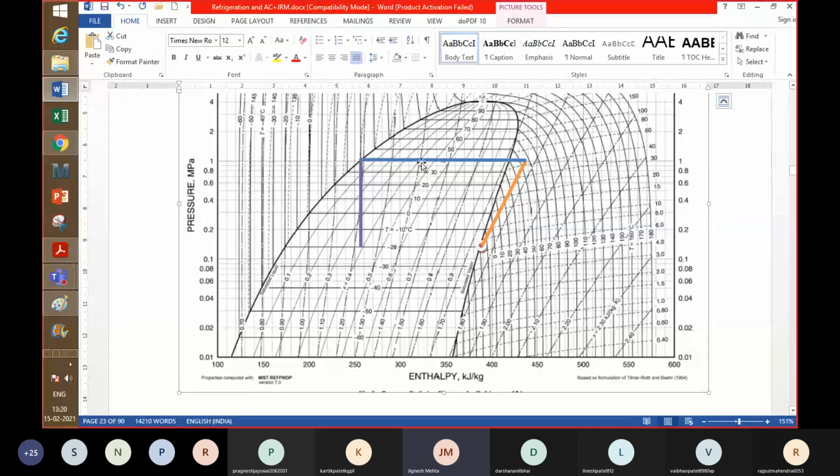Okay, and there could be other means also, but in a system where the pressure differential is not very high, you don't go for other means. Multi-stage compression could be possible, and at the end of the first expansion stage you take out the vapor, or such things are possible in an advanced VCR cycle. But if it is a small system, you are not going to implement that, and again if delta P is not very high, you are not going to increase the complications or complexities like that.